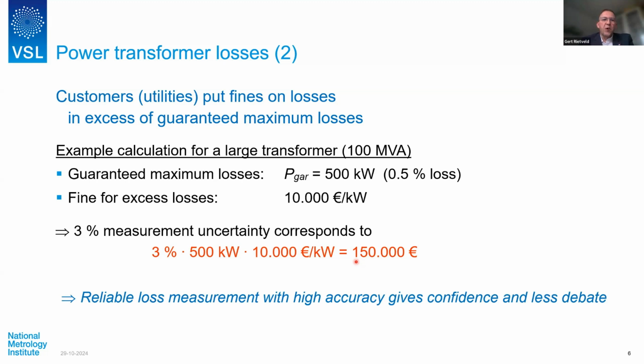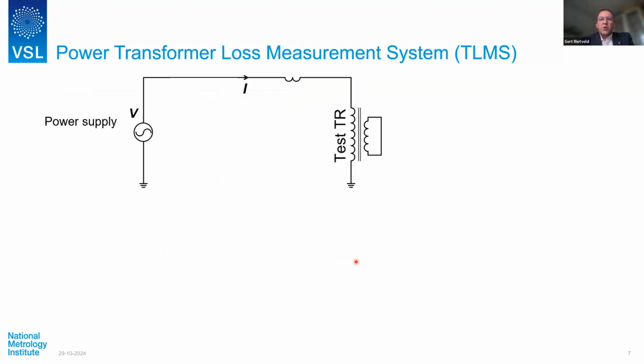So if you want to do a reliable loss measurement, you really need very high accuracy in order to achieve the confidence that you would like to get, and in order to minimize the debate between the customer, the utility, and the power transformer manufacturer that is producing the power transformers. So given this importance, the loss measurement of a power transformer is a very important part of a factory acceptance test of the product, of the power transformer.